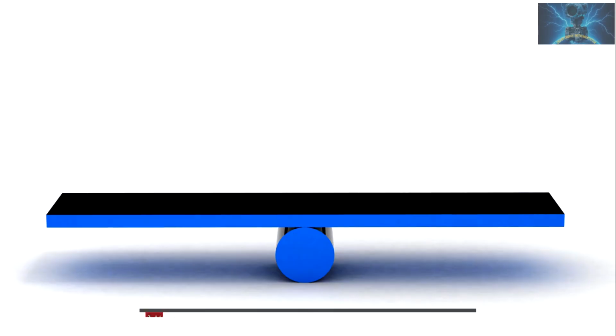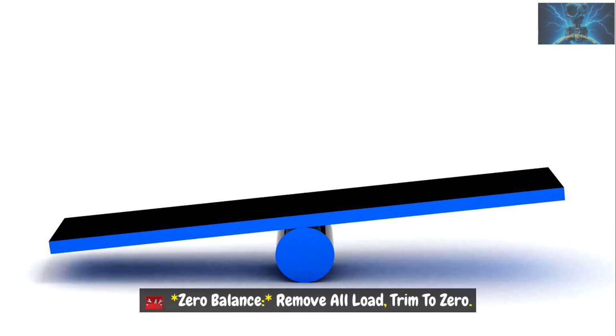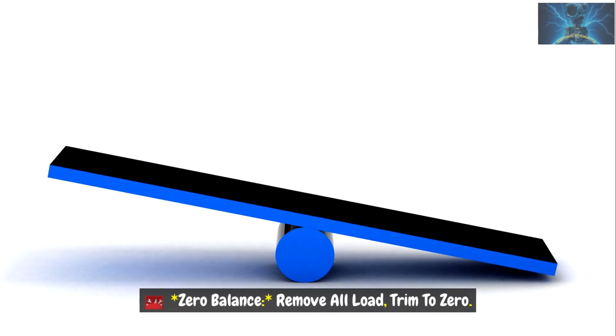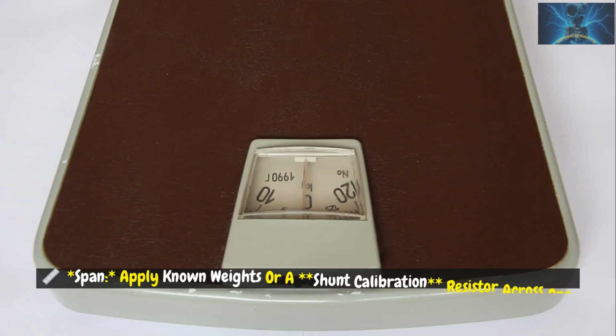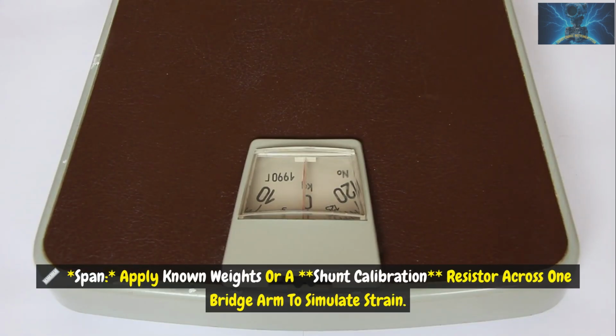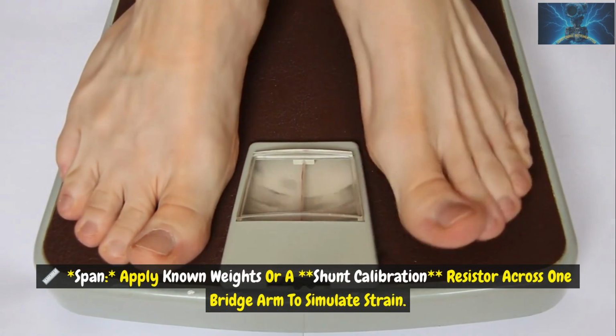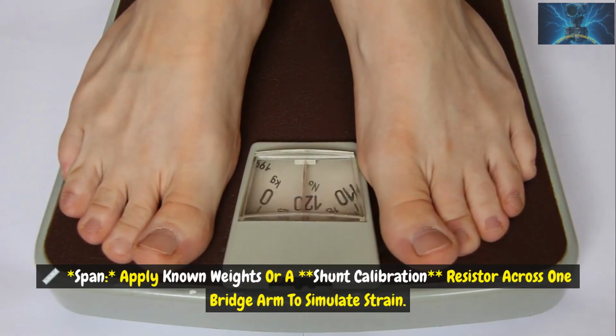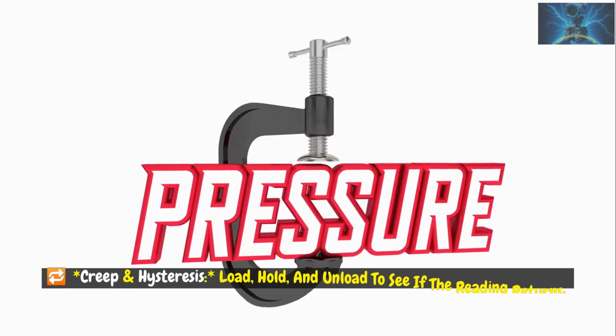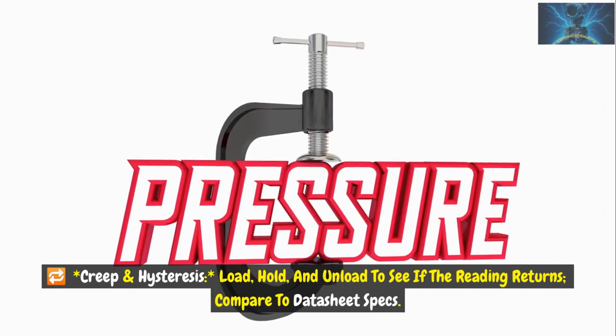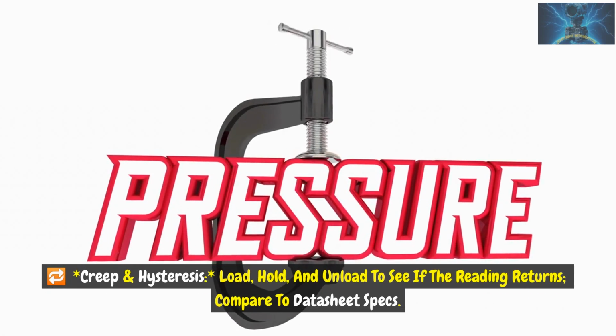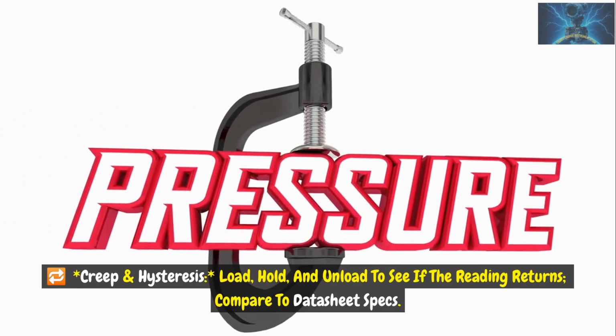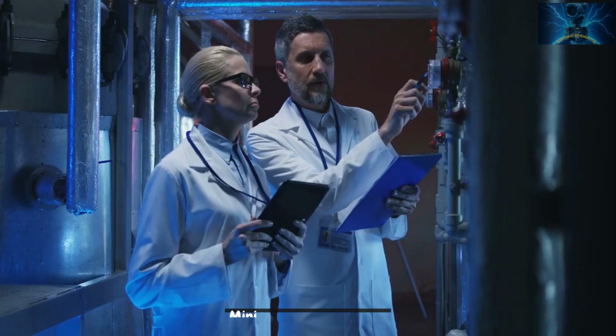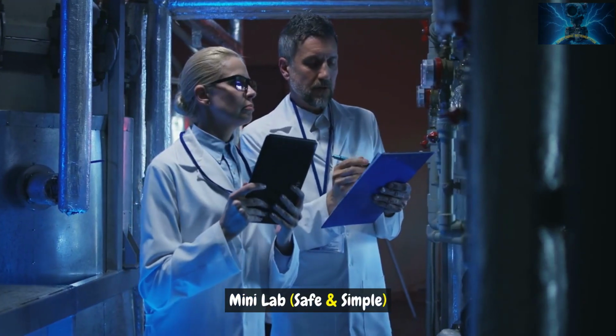Calibration and checks. Zero balance: remove all load, trim to 0. Span: apply known weights or a shunt calibration resistor across 1 bridge arm to simulate strain. Creep and hysteresis: load, hold, and unload to see if the reading returns. Compare to datasheet specs.